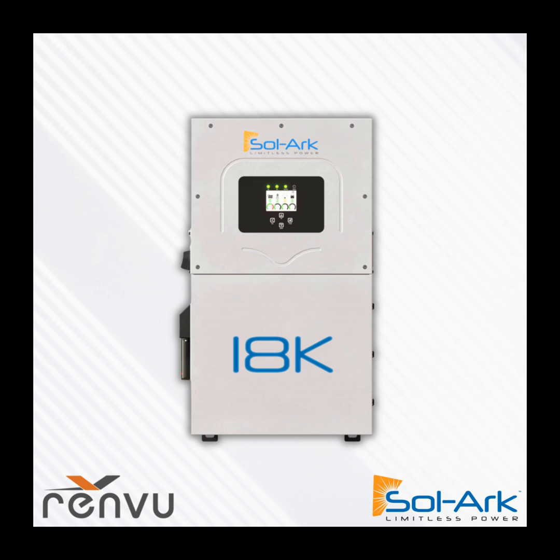However, where we do see customers using EVs with Sol-Ark is if the jurisdiction says adding an EV charger will overload your panel, so you'd have to upgrade to, say, a 400 amp service. With the Sol-Ark, you can say no, we're adding more power to the site, and we're going to land that EV charger onto the gen port. That adds more power to the system, gives you a convenient location for EV charger hookup, and backs up the EV charger so that if there's a power outage, you can still charge your car and get out of Dodge if you need to. So it covers a lot of bases for EV charging and pain points.